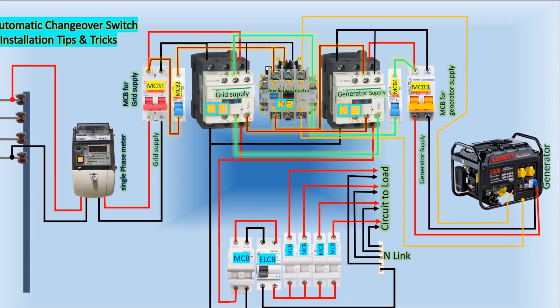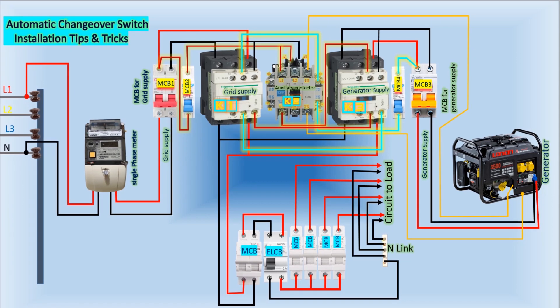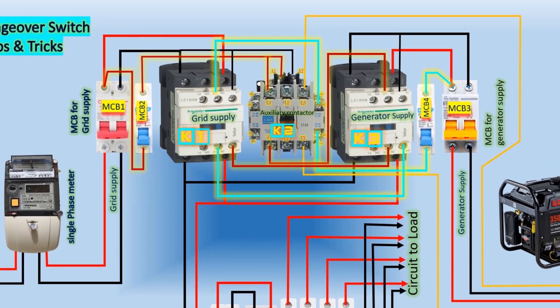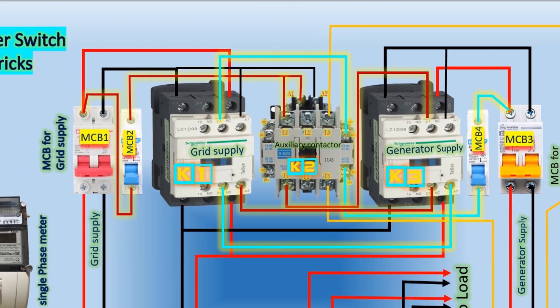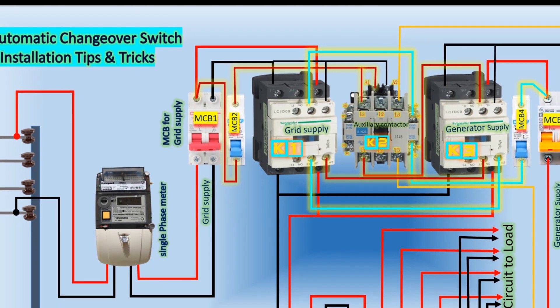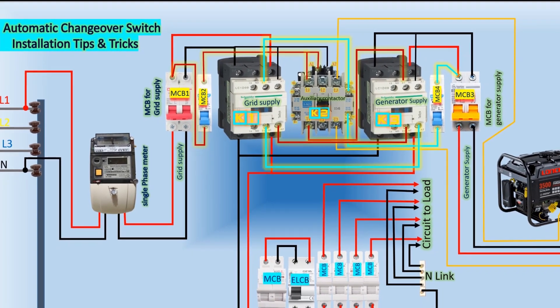When the main power supply is functioning normally, the ATS keeps the load connected to it while isolating the backup power source. However, in the event of a power failure, the ATS detects the change and initiates the switching process. It quickly opens the contact with the main power supply and, by starting the generator, activates the backup power source. If the generator is started, the K3 contactor operates and the generator power is connected to the load. If the grid supply returns, the ATS automatically reconnects the load to the grid supply, disconnecting the generator supply and turning off the generator.